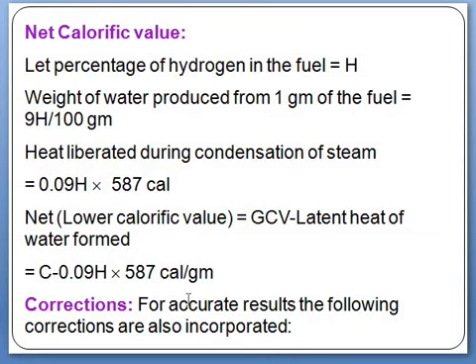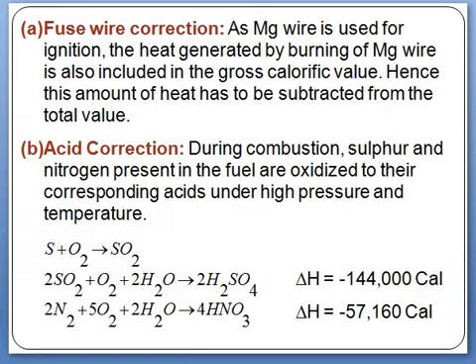For accurate results, the following corrections have to be incorporated. First, the fuse wire correction: since a magnesium wire is used for ignition, the heat generated by burning of the magnesium wire is also included in the GCV. Therefore, this amount of heat has to be subtracted from the observed value.